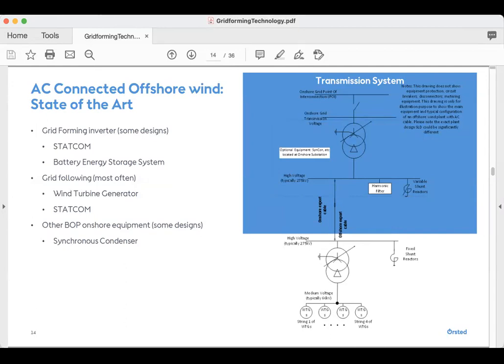And on the offshore end, we try to minimize our equipment as much as possible. Again, we want to restrict the offshore substation size and weight. So we put in some fixed shunt reactors, a very minimal amount that's required. And on the onshore side, we typically have harmonic filters, then variable shunt reactors, and of course a lot of balance of plant equipment like STATCOM. And in some of them, we also use battery energy storage. Again, we use the grid forming inverter technology for that. But most often our turbines are always grid following when it comes to offshore.